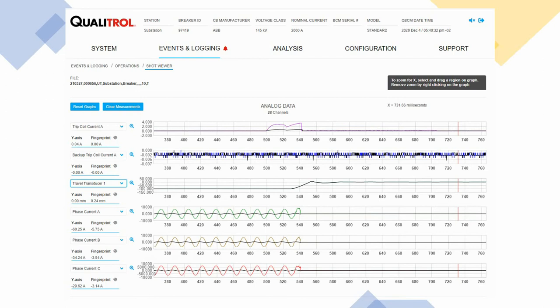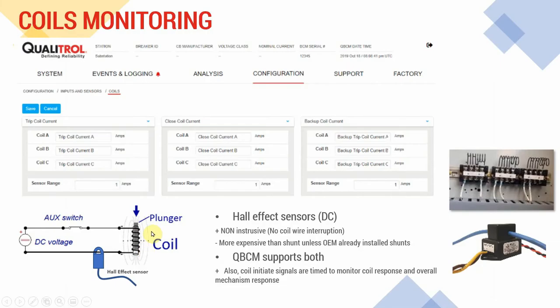There are two main applications of DC current measurement in breaker monitoring. The primary and the key application is the coils monitoring, or the solenoid coils monitoring. These coils are energized during an operation of the circuit breaker. Once they are energized, they make the plunger move that triggers the circuit breaker operation. So, the supply cable for these coils must pass through the opening of the sensor like shown here.